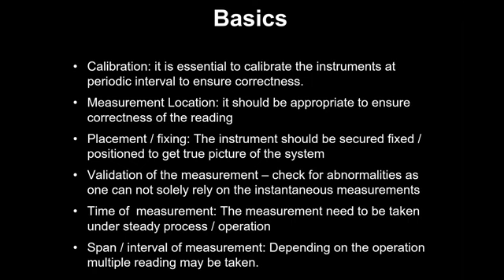Earlier, when we started audits, the normal length of the probe was 300 mm. Of course, I'm saying 20 years back, not today's situation. So the 300 mm probe was not even going inside properly to take the reading, because normally there is a 4-inch nipple, then 200 mm of refractory, then the casing, some insulation. So it was not even properly going inside the duct. It should at least go till the center or slightly less than the center, but it was just touching the circumference or somewhere in that range. That was the reason why we were not getting the correct value. Of course, now we have long stem probes, 700 mm, 1 meter length, so it's not a problem, but at that time it had happened.